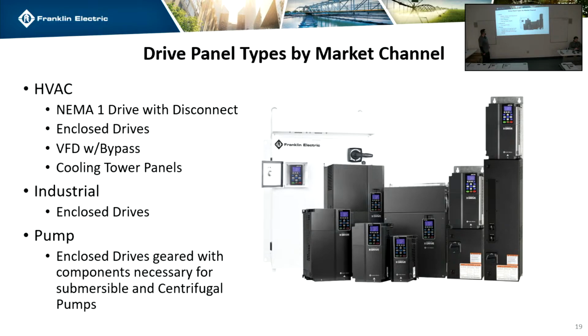And then for pumps, Franklin has a very, very large array of pump products, depending on who your salesman is what you're going to get. But we have standard panels for submersible and centrifugal that are already sized and ready to go for those two applications with Franklin motors. So what we've run into, guys, is that if you have like a booster, domestic water booster in a building that needs to be replaced, we can do that directly with Franklin.